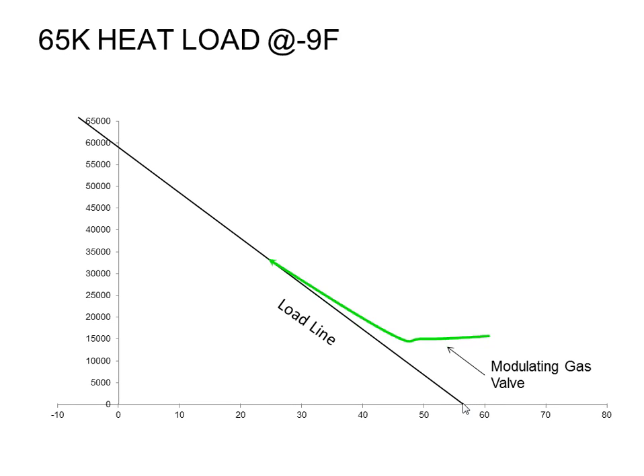He turns off his furnace, right? Everyone's going to be a little bit different based on how thermally efficient their house is and what kind of set points they like for their thermostat. But let's just pretend that this guy's house is our house. This green line represents what my furnace can actually do, right? So this guy, he's not going to actually directly look at outside air temperature. He's going to look at how close the space temperature is to the space temperature set point. But that's going to end up being a function of outside air. The colder it is outside, the more the gas valve is going to have to open to satisfy the space temperature, and then vice versa.